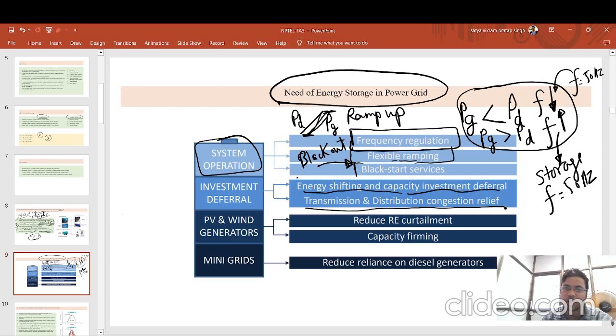This means that if you have certain storage devices in place, and there are transmission lines interconnected, and at one point of the grid the power suddenly ramps up, then the energy storage system can supply this extra demand in the grid in a shorter amount of time. So you don't need to depend on the far-end generator to ramp up power generation in response to a sudden increment in load demand - that is the kind of congestion relief provided by energy storage systems.